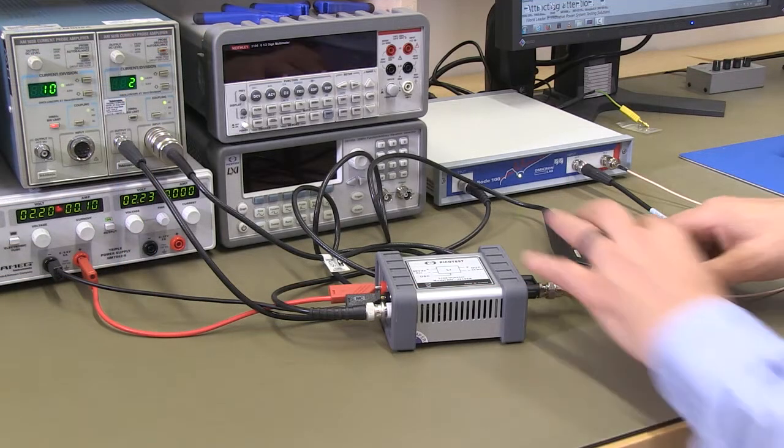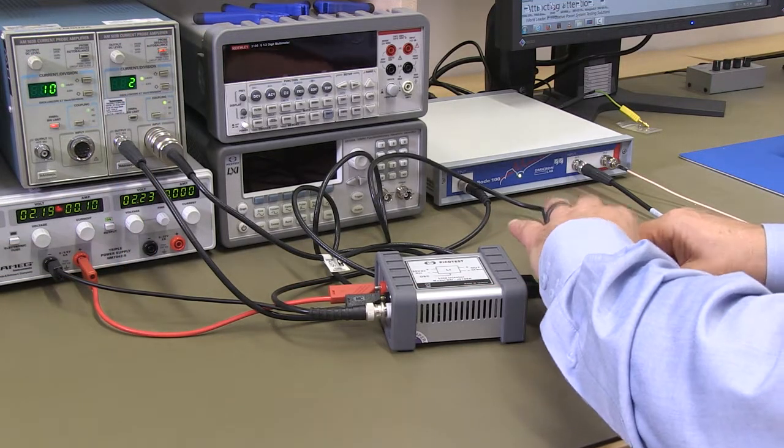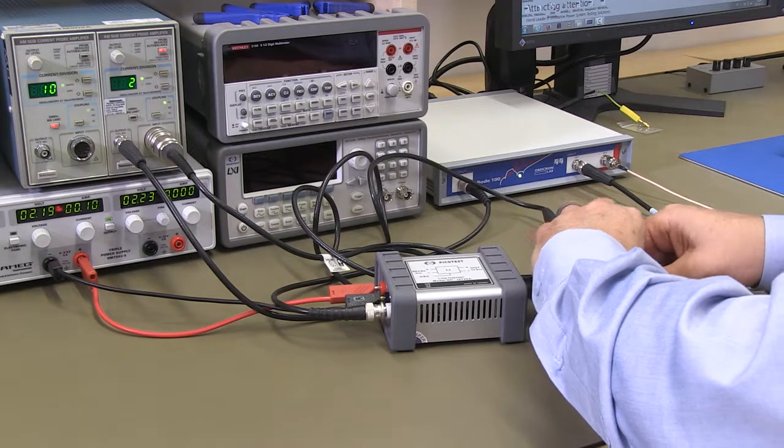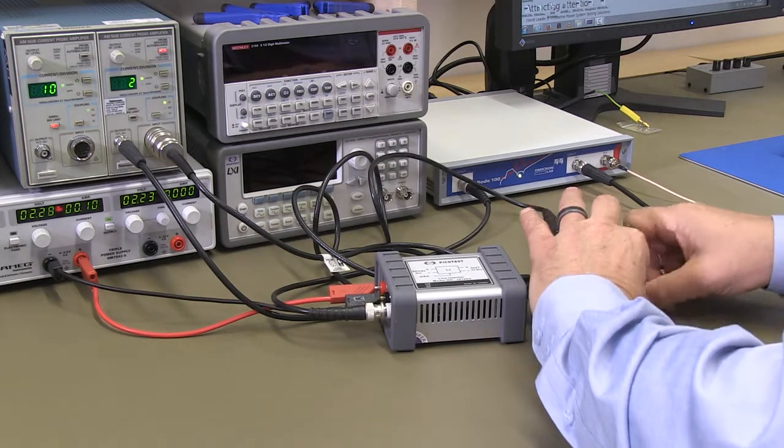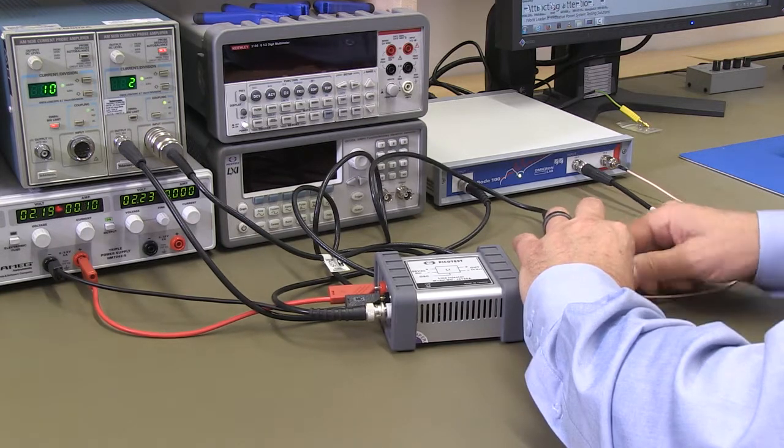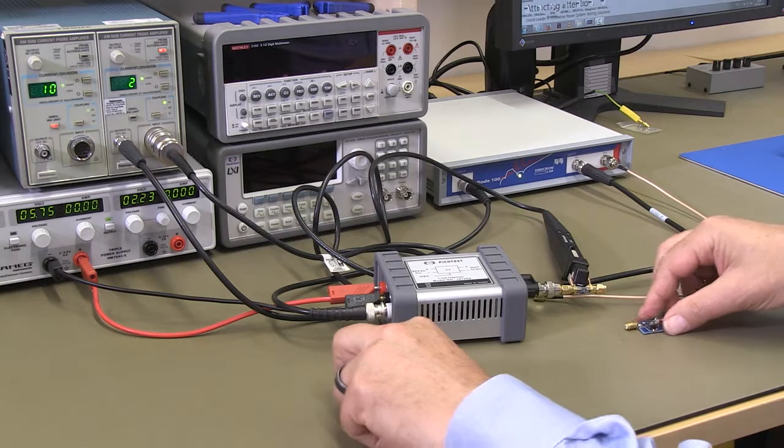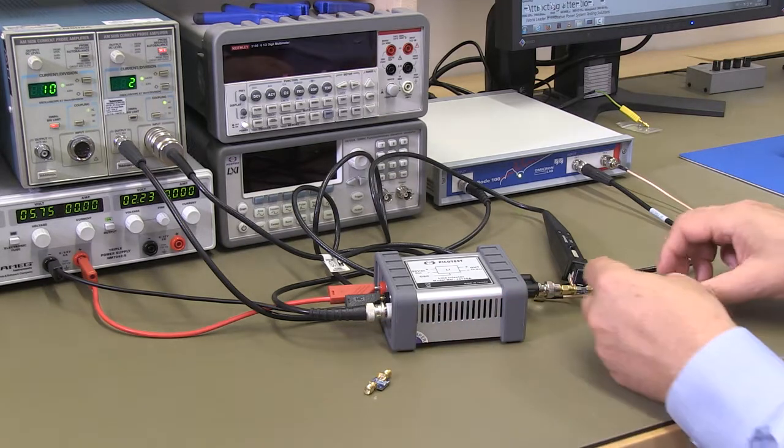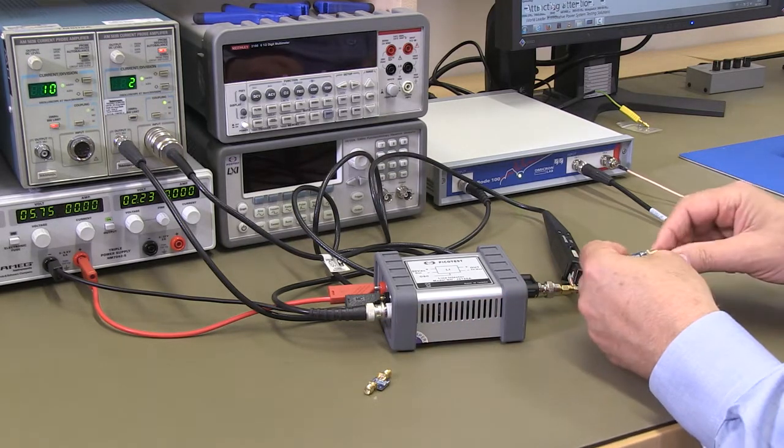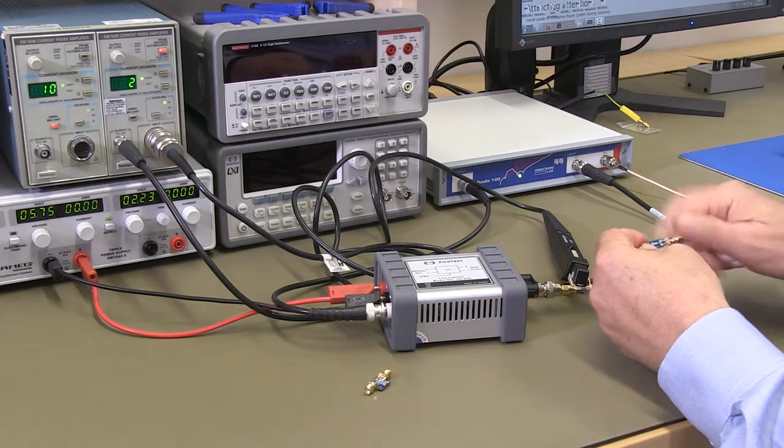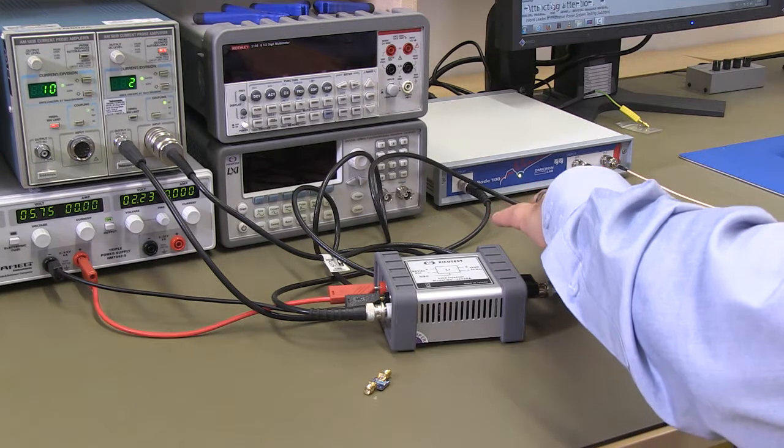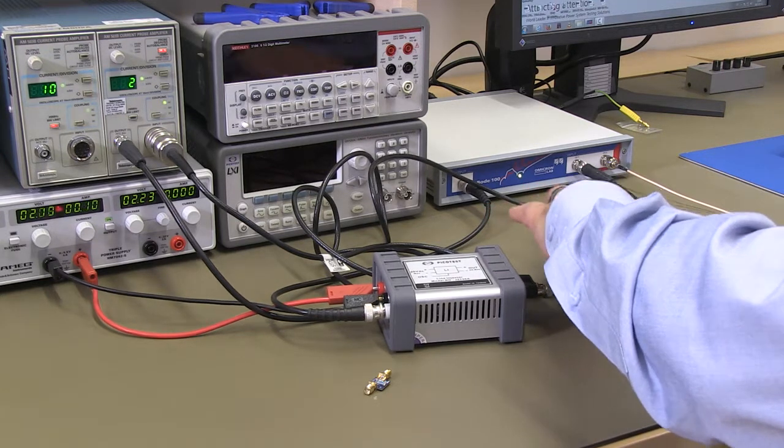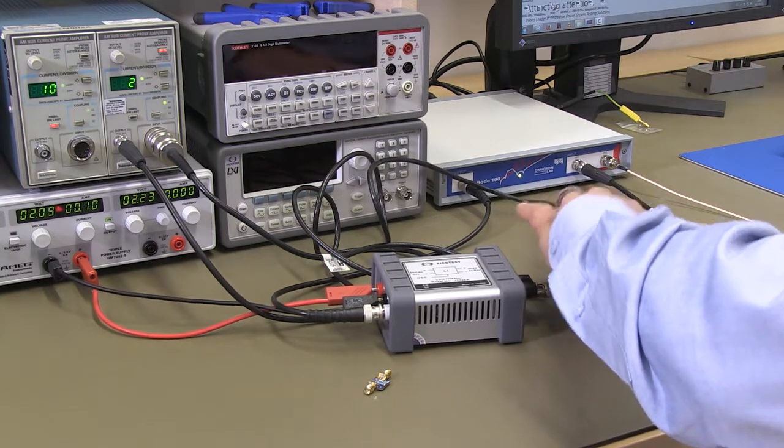So now that the calibration is complete, we'll remove our 1 ohm calibration resistor and we'll replace it with the inductor that we want to measure. Here we're using a 22 microhenry chip style inductor, and we've placed it into the measurement position.